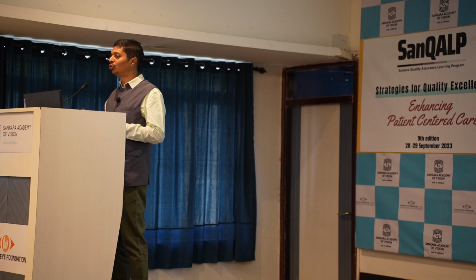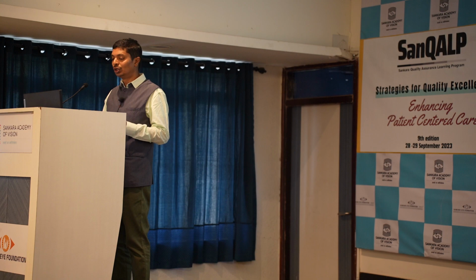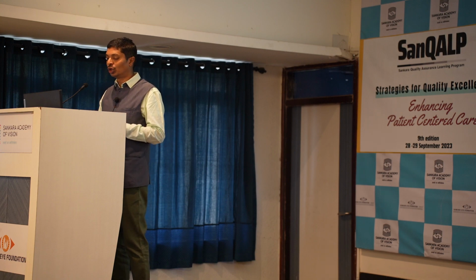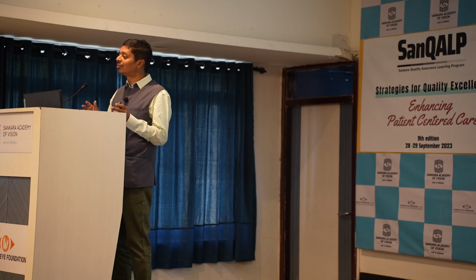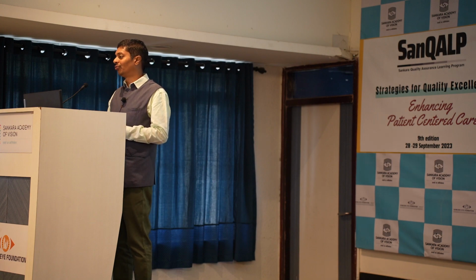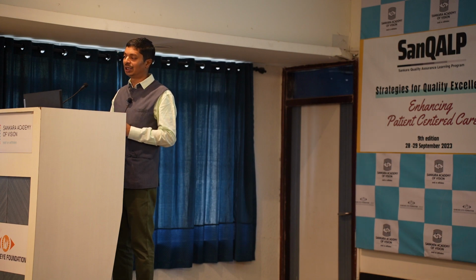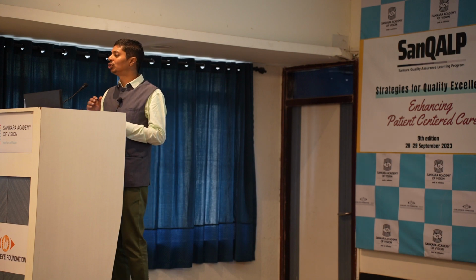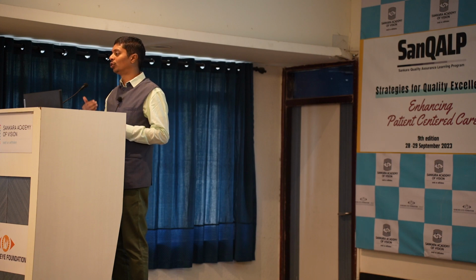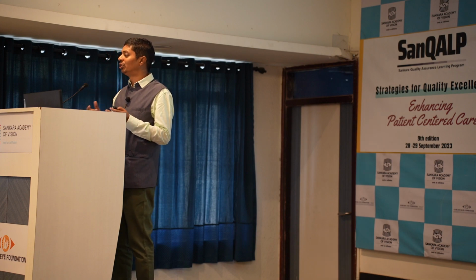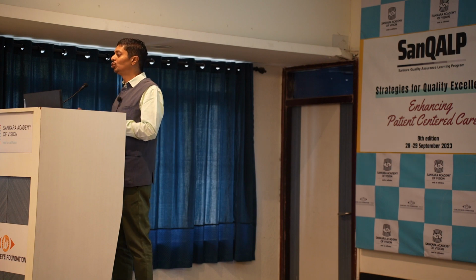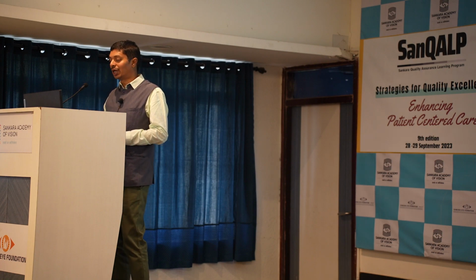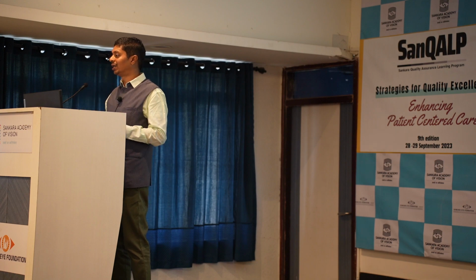When you are trying to do preventive or breakdown maintenance, you need to ensure how to remove the equipment so that accidentally it cannot be switched on. But there are some residual things that will be left. For example, if there is a capacitive circuit, there is energy stored, and if you accidentally touch it, it's going to discharge. There may be steam already in the chamber, which needs to be discharged.